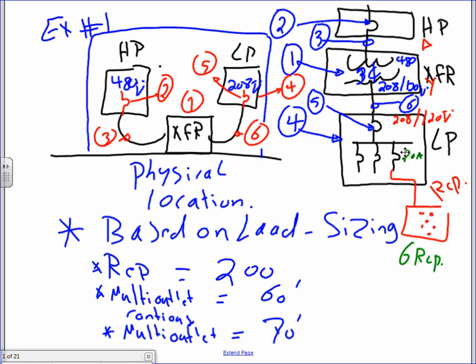Okay, now, here's how you start with your sizing. Number one, I'm giving you the following. When we size things, we always start sizing everything based on the load, right? What type of electrical load do you need in this building? In this case, because we're sizing for receptacles, everything is based on receptacles. I'm telling you that we hired Adam for this commercial or industrial building, and Adam went and installed 200 duplex receptacles, like the one in front of you right here. And then he put in multi-outlet assemblies. He put 60 feet of multi-outlet assembly, like the one on the wall right in front of you. This is continuous, where they will be continuously used. Multi-outlet assembly, continuously used. And 70 feet of multi-outlet assembly that's non-continuously used.